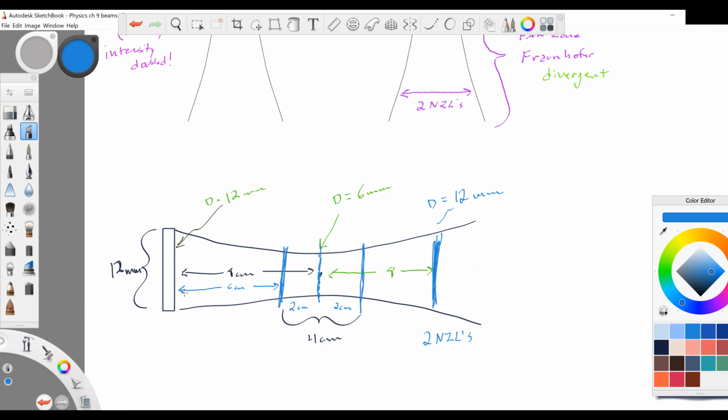Also called the focal length or near zone length, is the distance from the transducer to the narrowest part of the beam. Most modern ultrasound systems allow the sonographer to change the location of the focus. So we change from a natural focus to something else. We force it to focus somewhere else. But those are on phased arrays, multiple element transducers. However, early in development, we couldn't do that. So basically, we're still talking about single element transducers and how we make those changes.